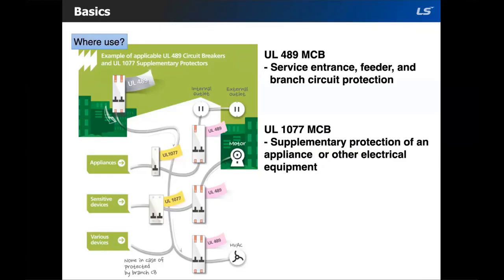UL1077 would be described as a supplementary circuit protector. These are not tested to the same standard as a branch circuit breaker. They only need to provide protection one time in testing. They are only intended to protect one single device, and they must be used in addition to the branch circuit protector.